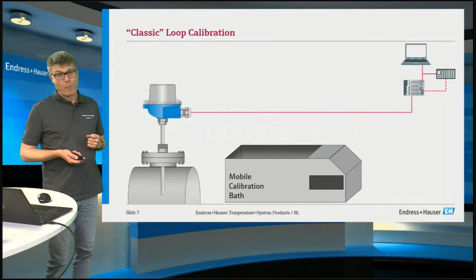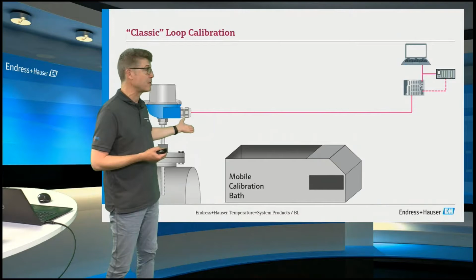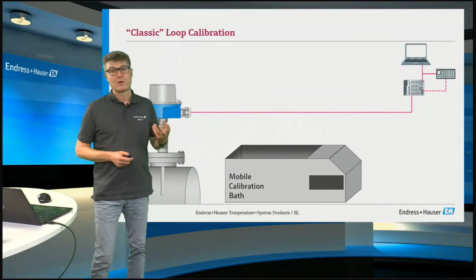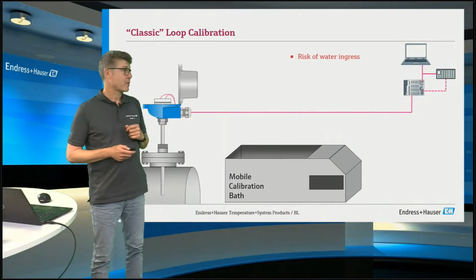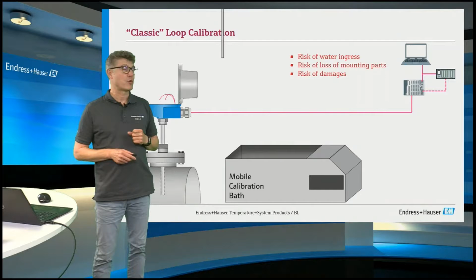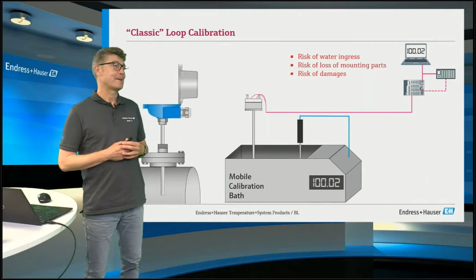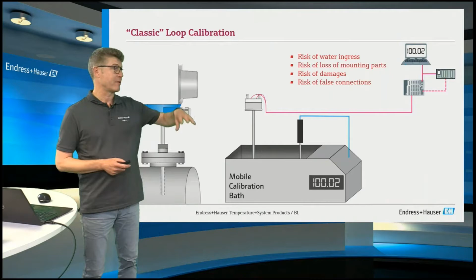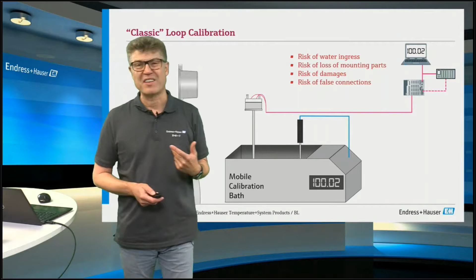So the typical way to perform a calibration like this is for a process temperature measurement, used in automation processes: an electrical thermometer wired to the control system. The typical way to do this is, you have to dismount it from your plant. You have to disconnect the cables by opening the head, opening all the terminals and screws. You place it in the block calibrator or the calibration bath, or you carry it to the lab. There it needs to be connected again. You perform your calibration using the reference and so on. And at the end, you have to do it the other way around, connect it in the plant again and so on.